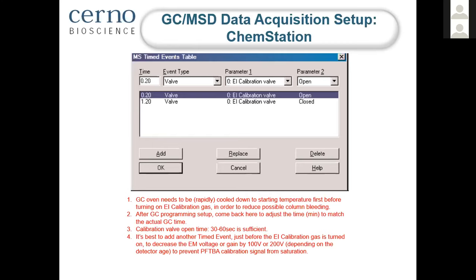And then after the GC programming, you want to come back here to adjust the time, the minute, corresponding to when you want to turn the valve on and when you want to turn the valve off. We typically suggest 30 to 60 seconds is more than enough at the end of the run and after the GC oven is cooled down.